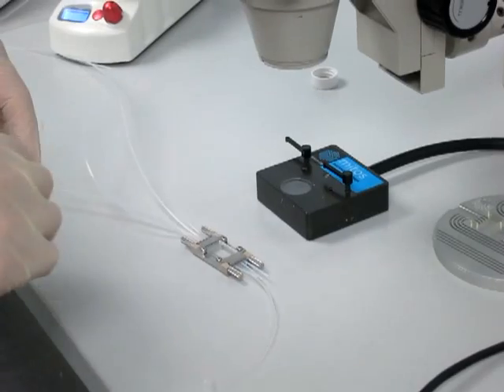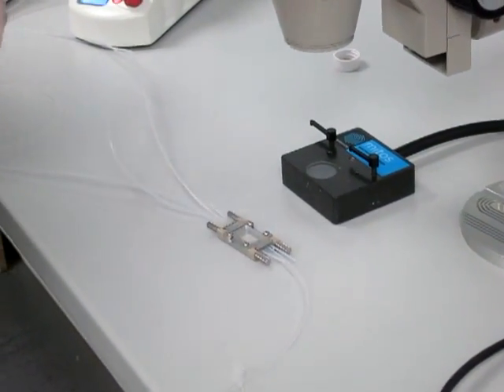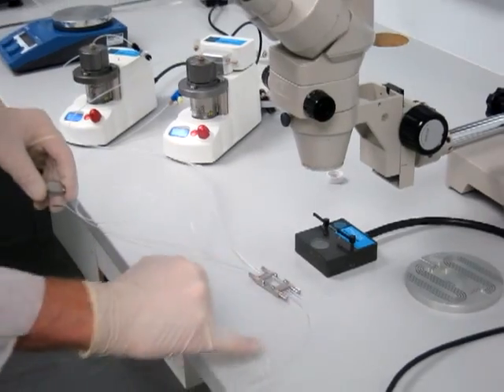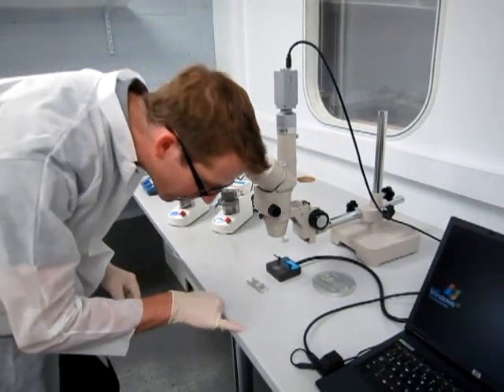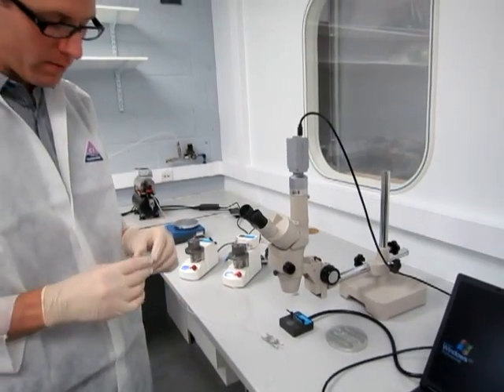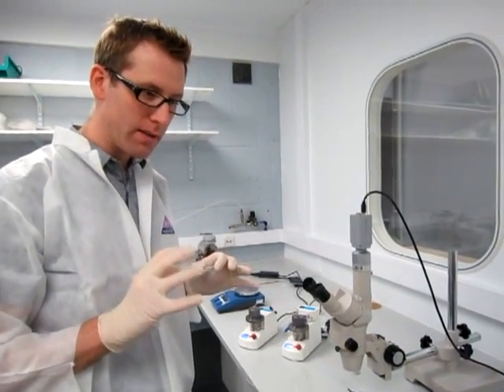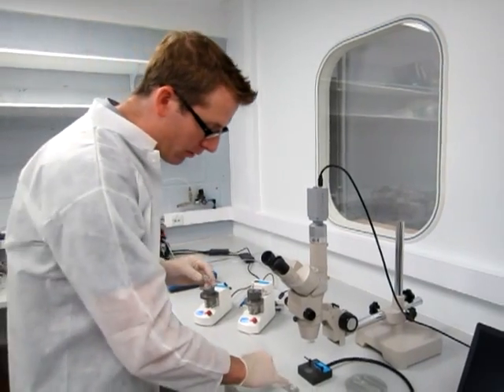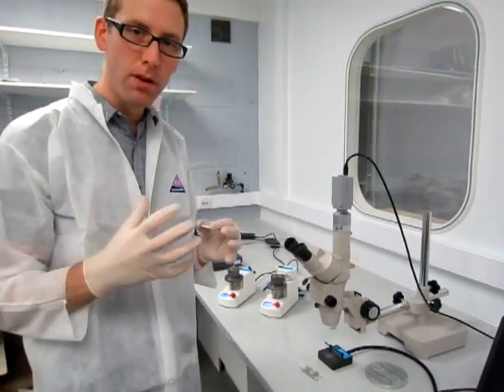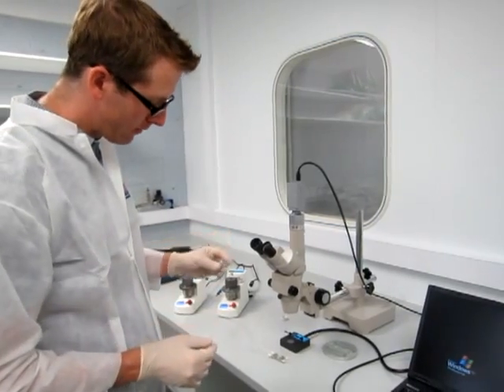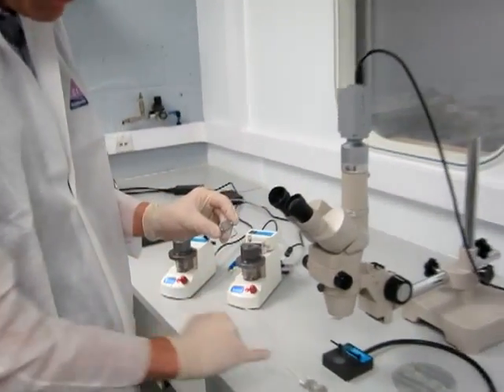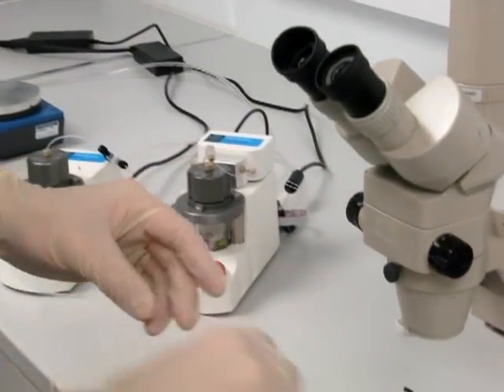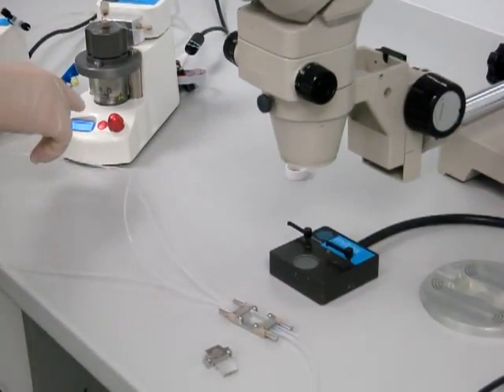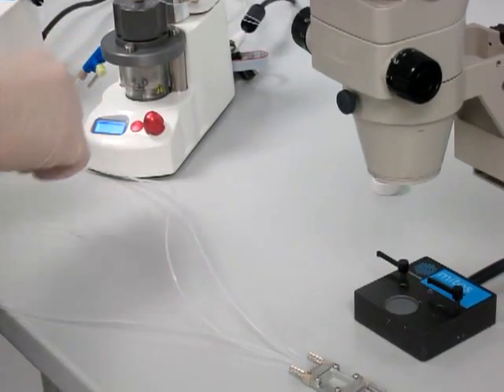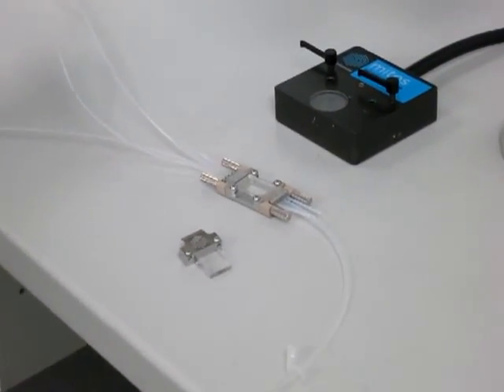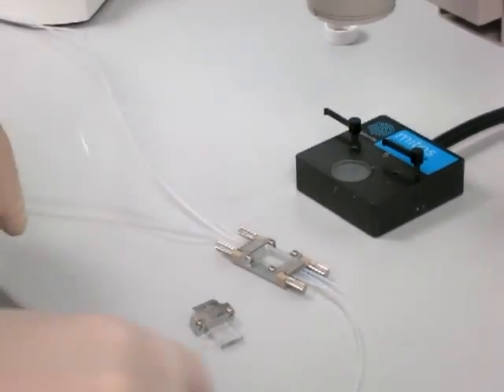One of the potential issues is when you come off the chip, if you've got a good surfactant, then the droplets will go into the tube and you'll collect this up. You can see there's some emulsion being collected there. In some cases, if the surfactant isn't as strong, then when you go from the chip to the tube, you sometimes get some coalescence or merging of droplets. So we also have a version of the chip which, rather than fitting in the holder, has a header. I'll just demonstrate this quickly. I'll just depressurize. Okay, so I just vented those.